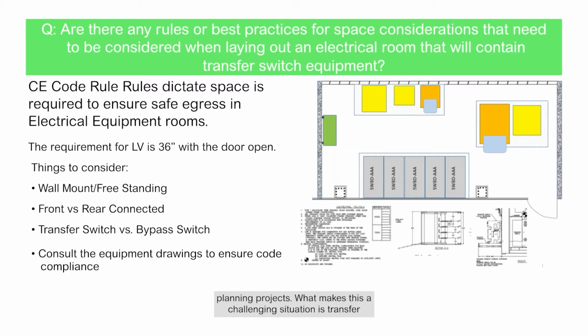What makes this a challenging situation is transfer switches come in many sizes and shapes and types, as do electrical rooms. Take into consideration that some equipment requires front access while others require rear access. Some switches are going to be wall mounted and some are going to be floor mounted.